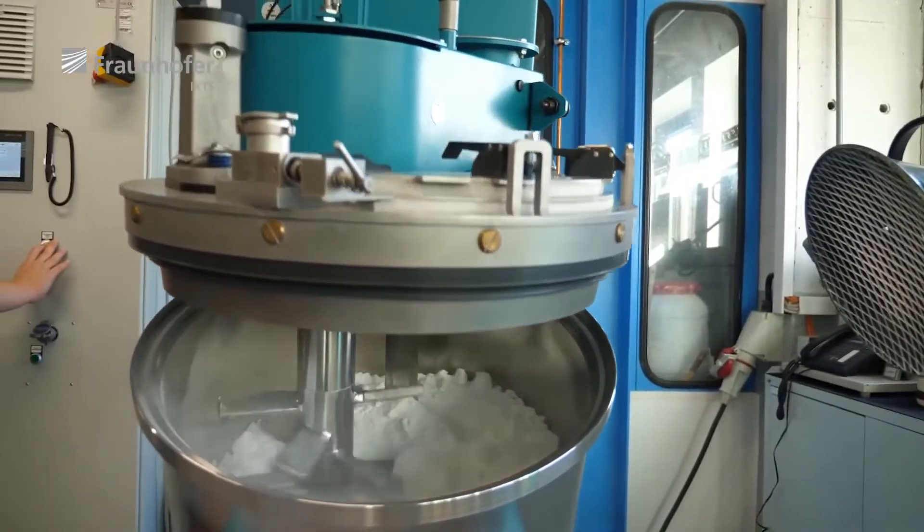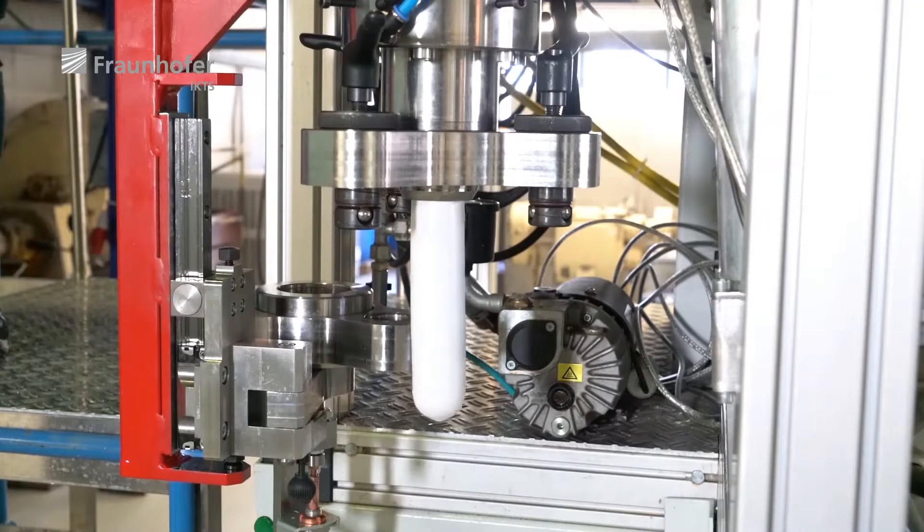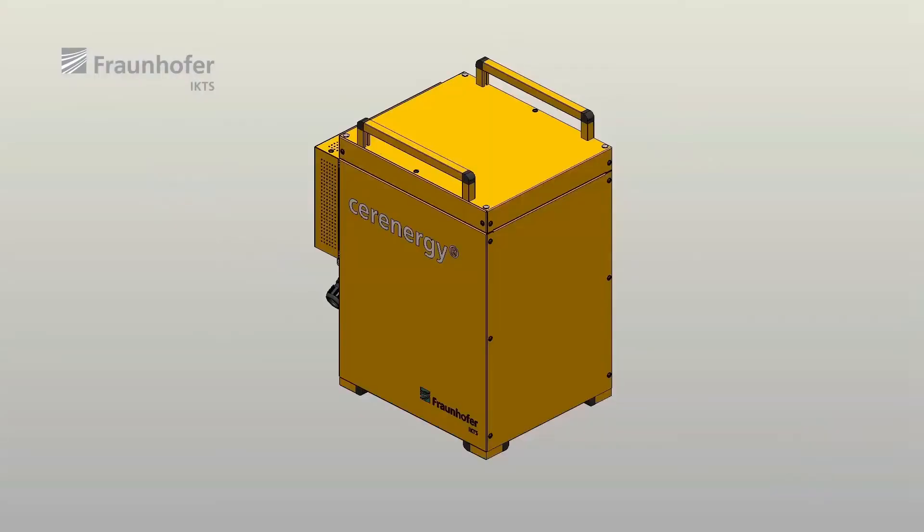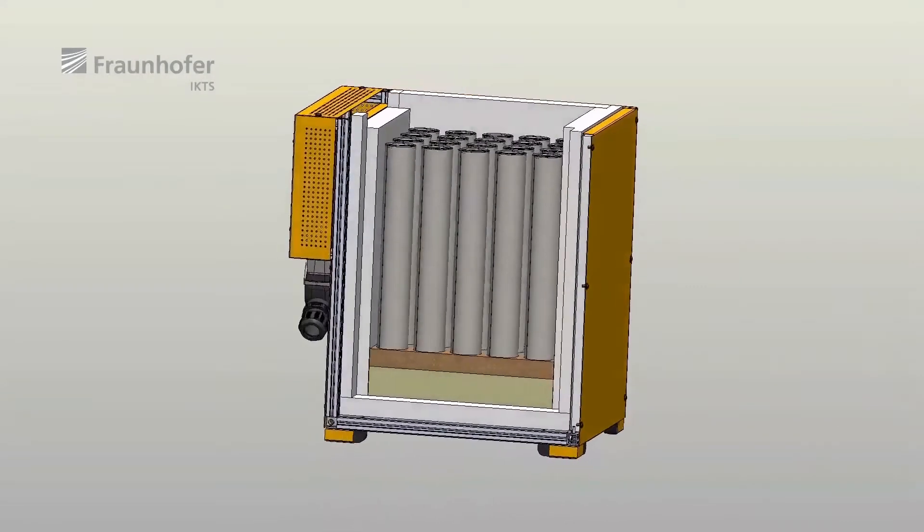The nickel is reduced back to metallic nickel. As you can see from the cerenergy battery chemistry, there's no flammable liquid electrolyte, as there is in lithium-ion batteries. Instead, a ceramic solid-state electrolyte is used. As a result, the battery is totally fire and explosion-proof, and it's resistant to thermal runaway.